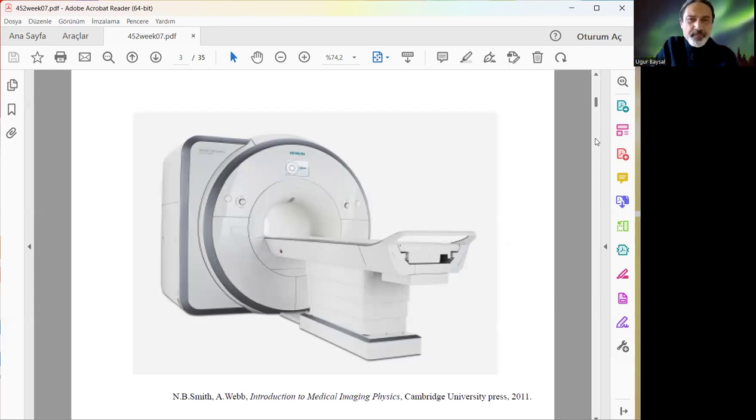So, this is the general view of the system where the patient is placed into the imaging system in a supine or lying down position. There's a patient bed, there's a big hole having a great DC magnetic field. So there's an invisible force in the system which could result in great and damaging forces due to the high strength DC magnetic field. So there are some precautions.